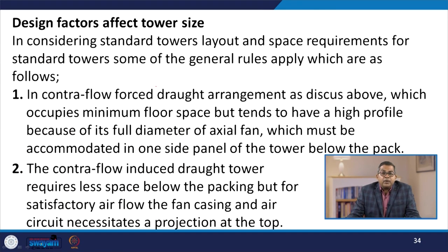Now, let us talk about the design factors that affect the tower size. While you are considering the standard tower layout and space requirement for standard towers, some general rules prevail for the design of these cooling towers. One is the contra-flow forced draught arrangement, which we have already discussed, which occupies the minimum floor space but tends to have a high profile because of the full diameter of the axial fan, which must be accommodated in one side panel of the tower below the pack, if you recall the figure.